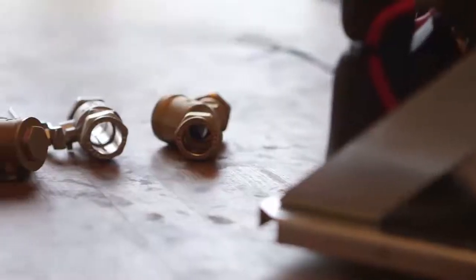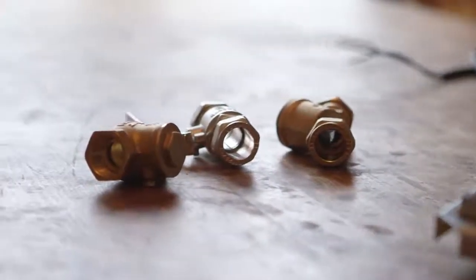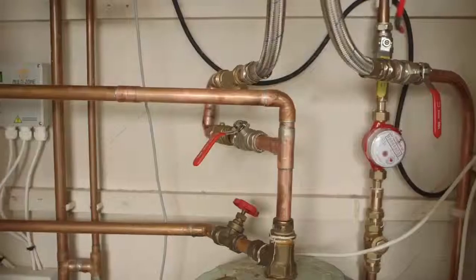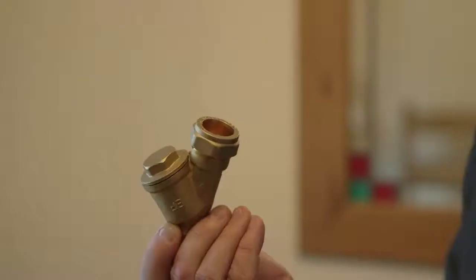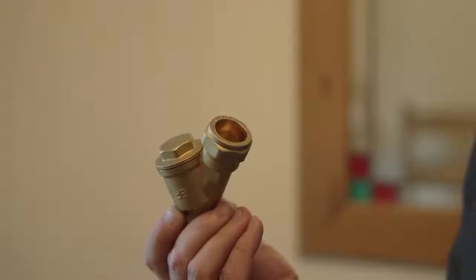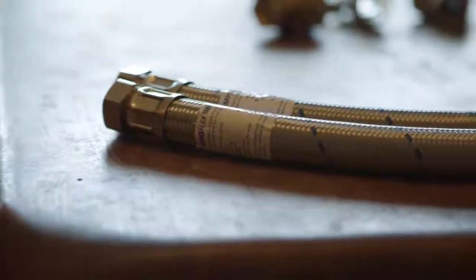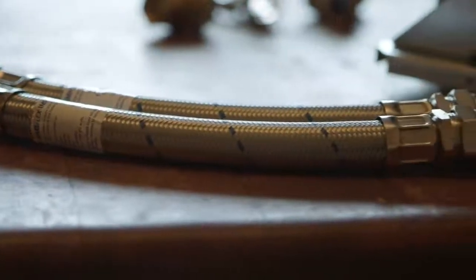We also recommend the installation of 2 lever valves on the water flow and return. On a vented system where there's low pressure, a flappy paddle or penny type non-return valve. As we use a plate heat exchanger, we recommend the installation of a Y filter to stop any possibility of contamination. All the components in the Globus pack have been specially selected for their quality. We highly recommend that they're used in the fitting of the box.